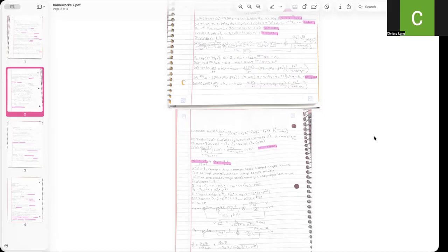Finally, we evaluated whether the controller needs retuning when operating conditions change. If concentration span or flow relationships change, gains in the loop change, so the controller should be retuned. However, if only the transmitter zero shifts but the span remains constant, the dynamic response of the loop does not need to change. So it is not necessary for that final one.